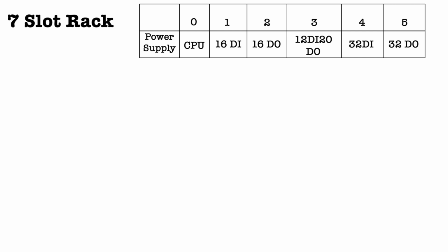Okay, so for the 16 digital inputs, it's simple: I:1.0/0 to I:1.0/15. And for the 16 digital outputs in the second slot, how can they be addressed? Similarly to what we did, O:2.0/0 to O:2.0/15. So in this way we can address the 16 digital inputs and outputs. Okay, I think this is clear for you.